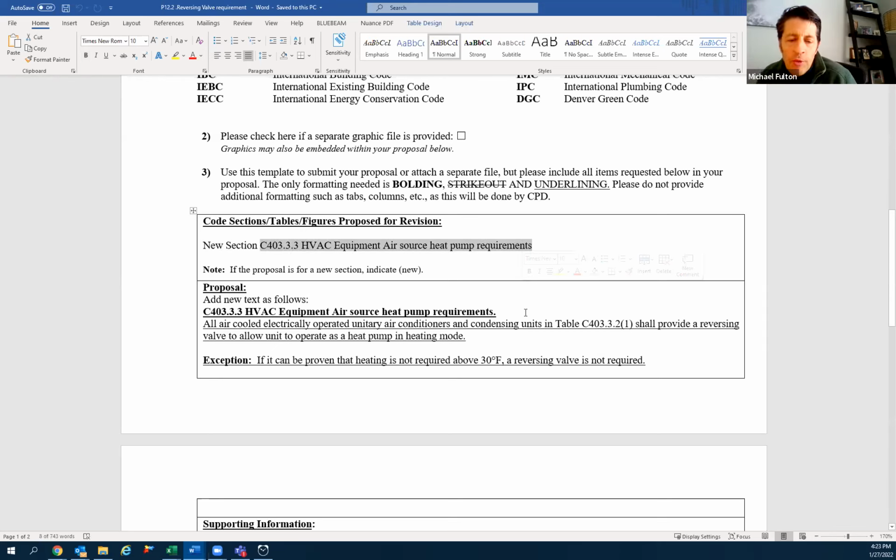Yeah, so the concept here was if you're replacing a rooftop unit, you would basically do what's called a dual fuel. Say you had a gas unit and you were putting in DX, you would do a heat pump with gas, where the heat pump would operate down to say 30-degree ambient, when Xcel's grid is really clean. And beyond that, you could use gas because Xcel doesn't really have the capacity yet to go full electrification. So that was the concept.